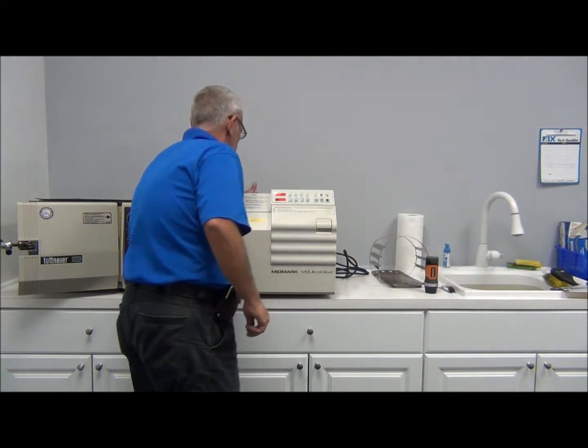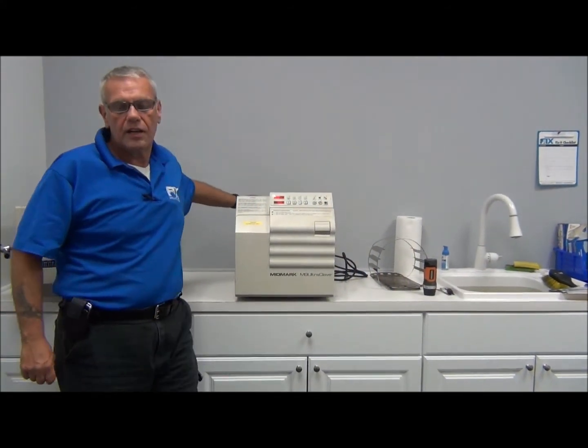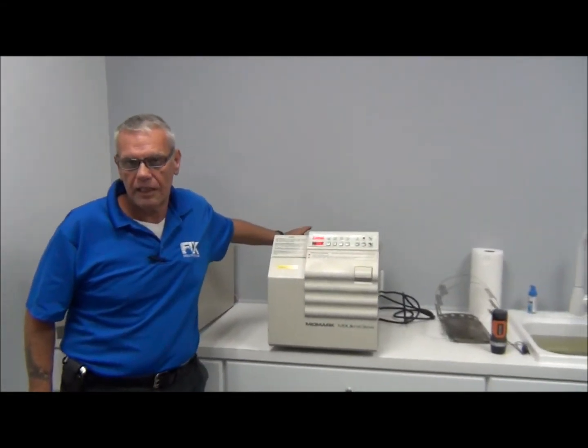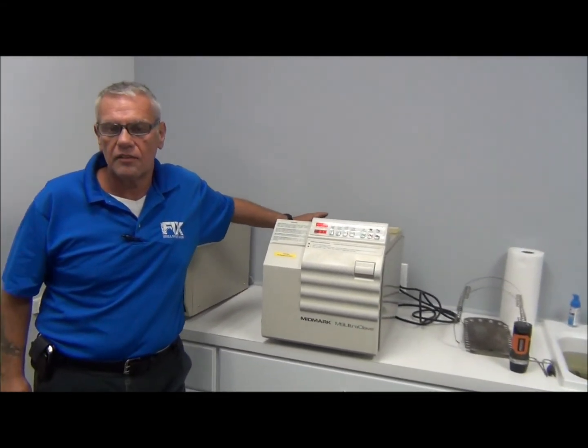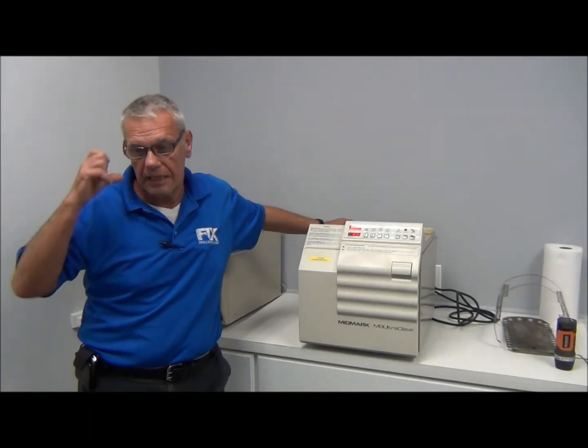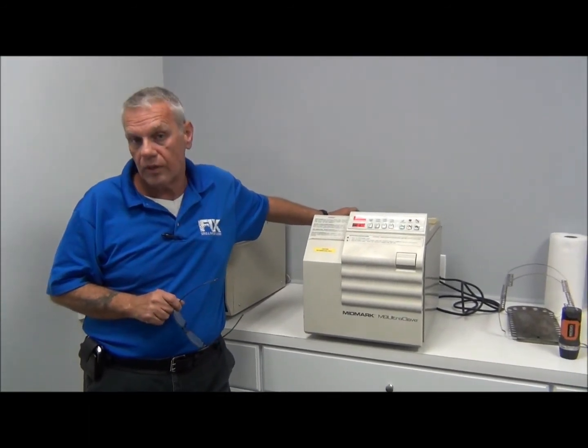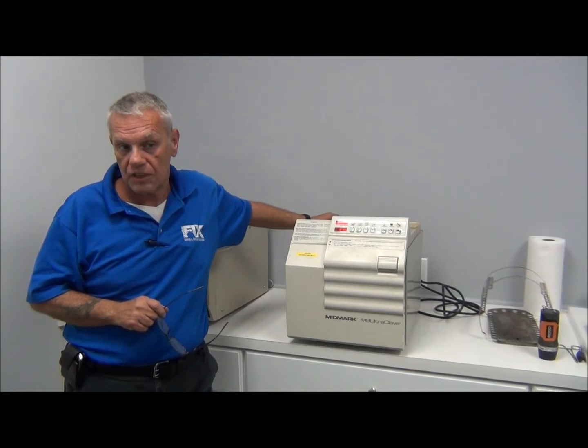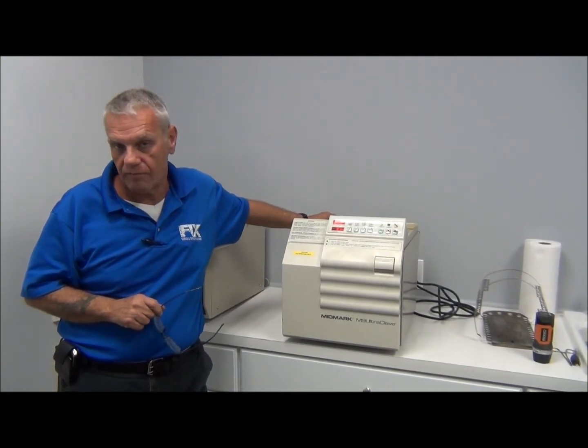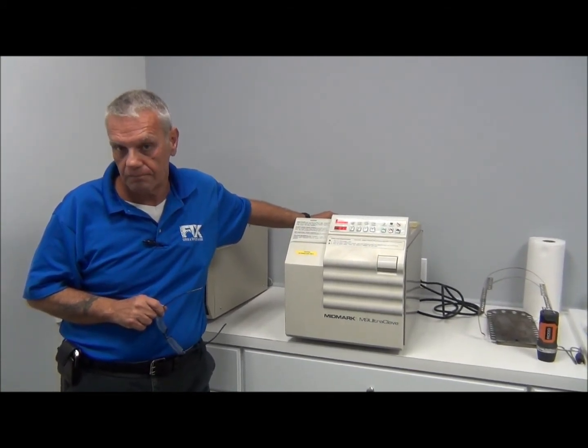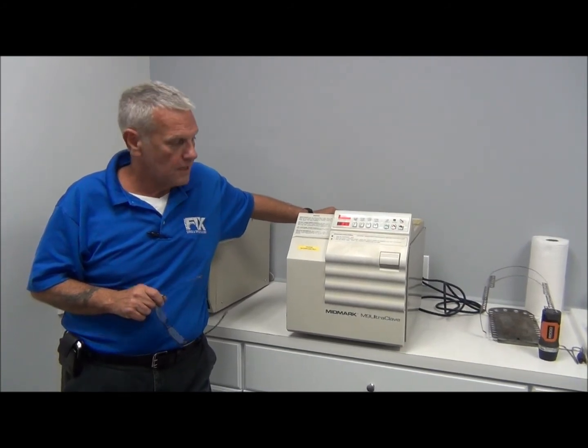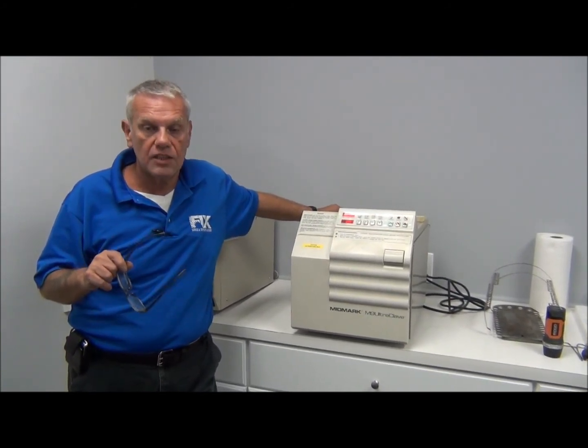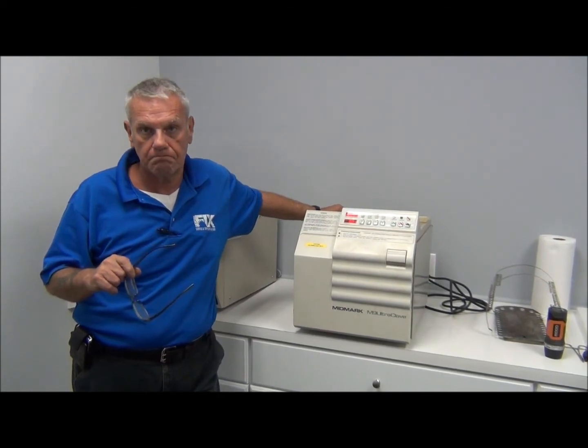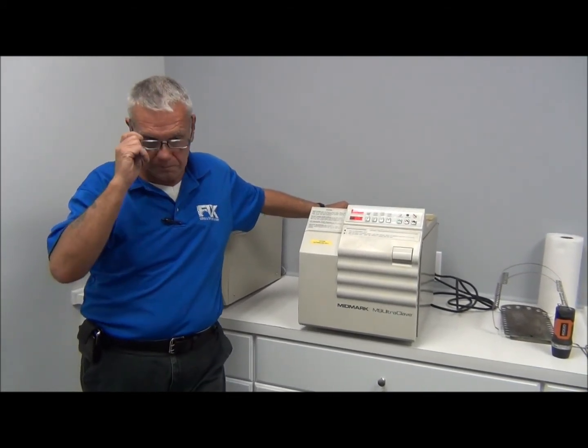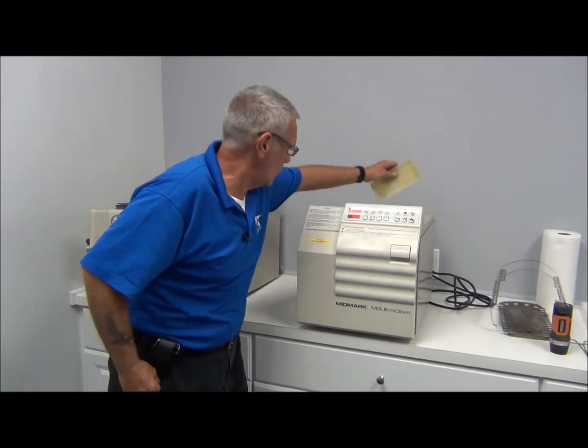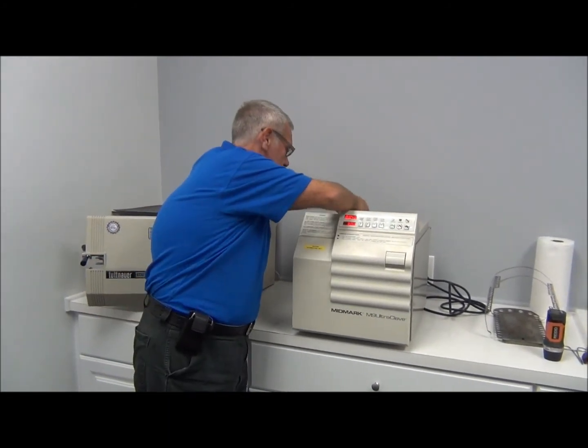In our reservoir, we do not hear the steam trap escaping anymore. We don't see a lot of unusual condensate from the steam trap. The steam trap should close between 190 and 210. The steam trap is not available in the preventive maintenance kit. That's another service call, okay? So essentially we have performed our PM. What we're going to do is reassemble the reservoir top, thusly.